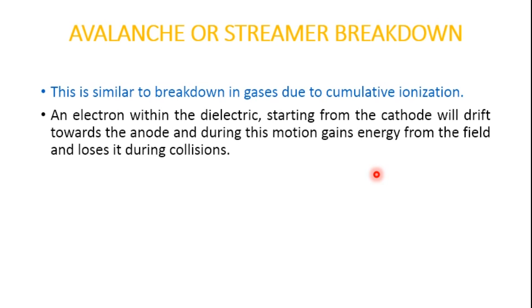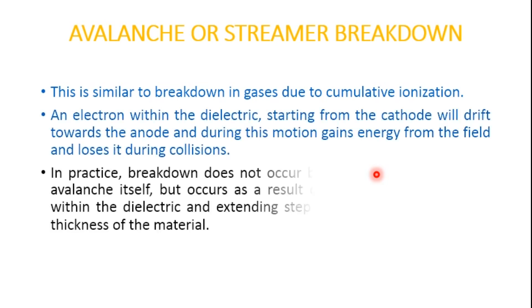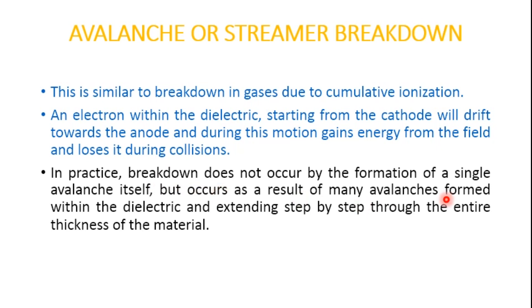Breakdown occurs when the avalanche exceeds a certain critical size. In practice, breakdown does not occur by formation of a single avalanche, but as a result of many avalanches within the dielectric extending step by step through the entire thickness of the material. Free electrons move from one atom to another, collide, gain energy from the electric field, and lose part of their energy. When this happens continuously, too many electrons are liberated, resulting in an avalanche between the two electrodes, eventually initiating streamers.